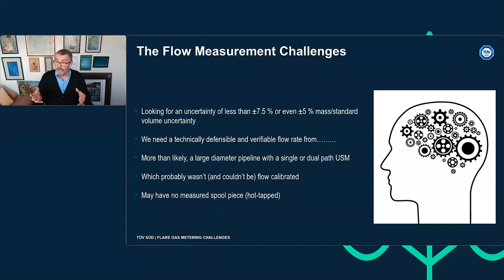And more than likely, it's got a complex inlet piping geometry. And that will give rise to significant installation effect biases. The flow will not be traveling through the pipe in an ideal manner. So the challenges just keep coming for flow measurement. It's probably operating with no live gas composition information available, unlike a gas export system, which will more than likely have a very accurate and very up-to-date composition coming from a gas analyzer. That's not very often the case for flares. It's a sample that was taken 3 years ago, or the operator uses the gas export sample or the fuel gas composition. So these all increase the uncertainty.